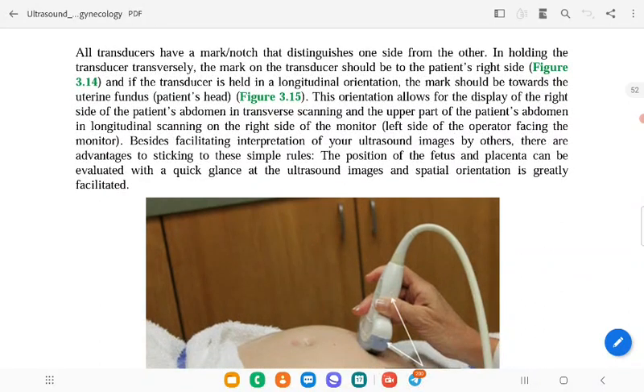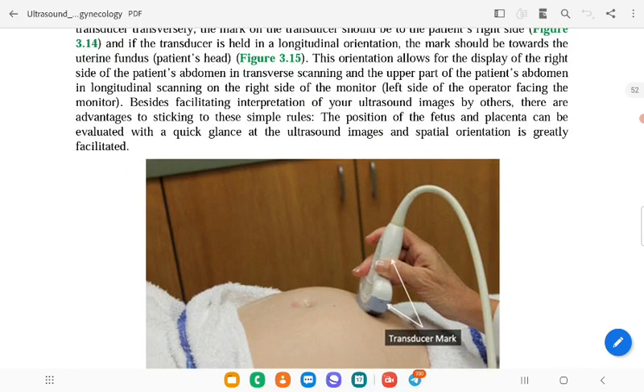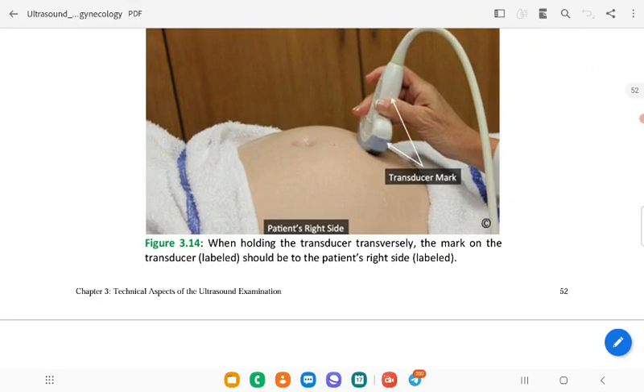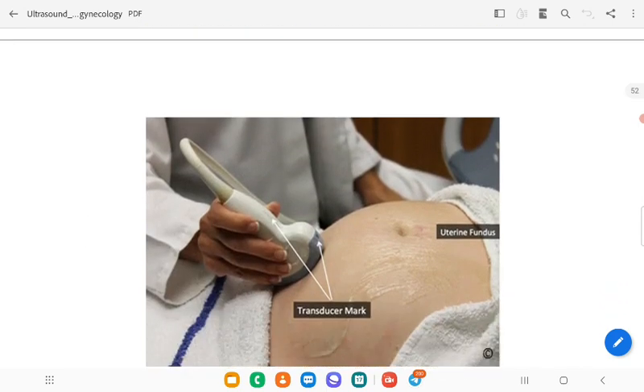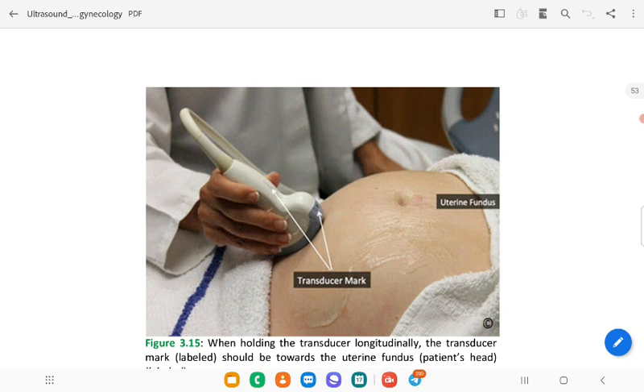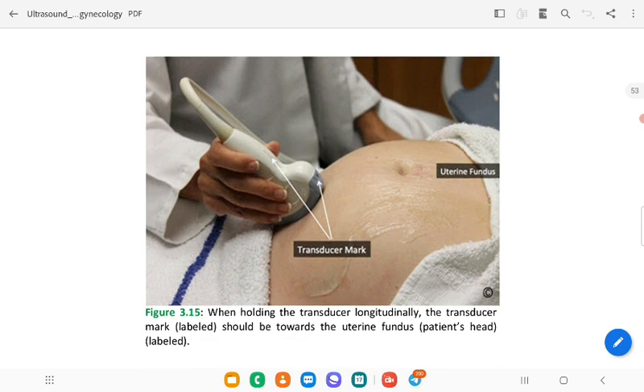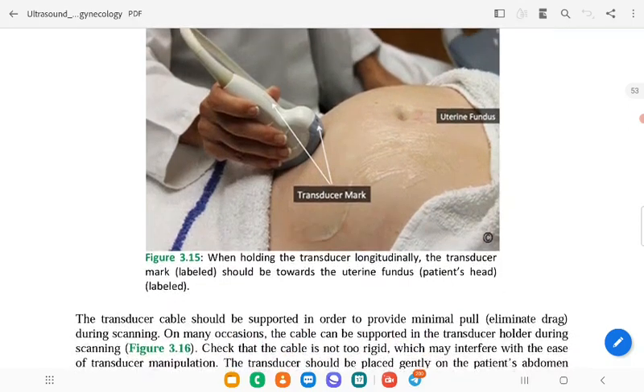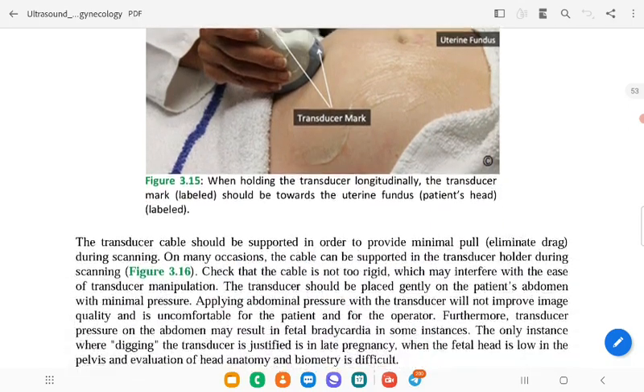Besides facilitating interpretation of your ultrasound image by others, there are advantages to sticking to these simple rules. The position of the fetus and placenta can be evaluated with a quick glance at the ultrasound image, and spatial orientation is greatly facilitated. When holding the transducer transversely, the mark on the transducer should be to the patient's right side. This is the uterine fundus transducer mark. When holding the transducer longitudinally, the transducer mark should be towards the uterine fundus, the patient's head.